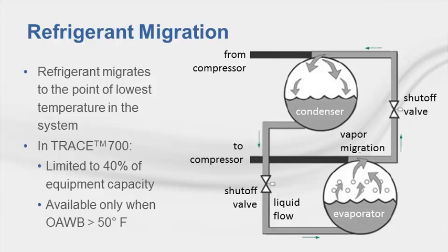Finally, there's refrigerant migration. When returning tower water is colder than the chilled water temperature, refrigerant pressure in the condenser is lower than that of the evaporator, driving the boiled-off vapor into the condenser. Once the refrigerant condenses, it flows back into the evaporator by gravity so compressor operation is not necessary. When modeling refrigerant migration in TRACE 700, keep in mind that the free cooling available is limited to 40% of equipment capacity, and if the cooling load cannot be met by refrigerant migration, the load is satisfied using the conventional cooling cycle.